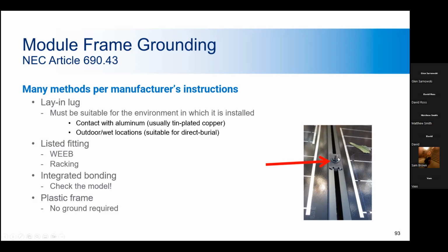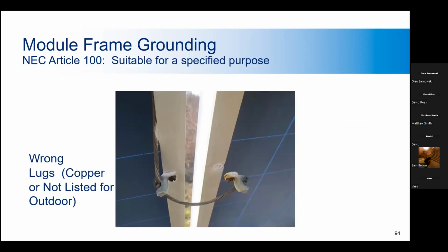Here we see an integrated mid clamp that provides bonding of all the modules, except that in this installation there was one single module placed by itself, which would need a separate bonding method, and they did that using end clamps. There are other methods, such as WEEB washers or star washers, that may also accomplish the bonding and grounding, as well as actual lay-in lugs, which we'll see a little bit more in a minute.